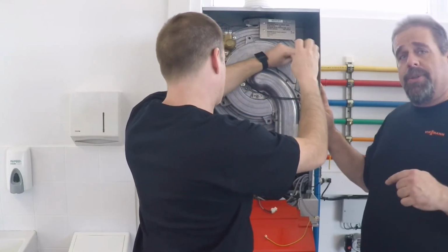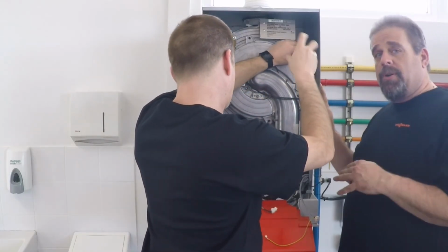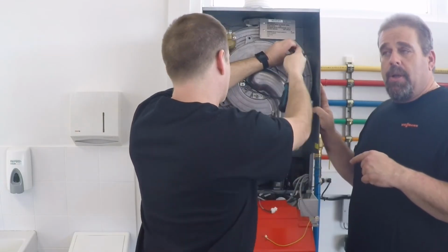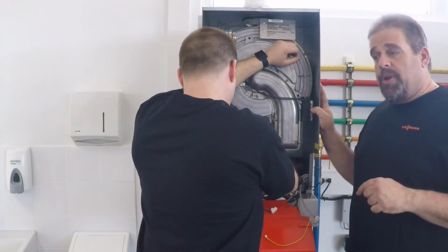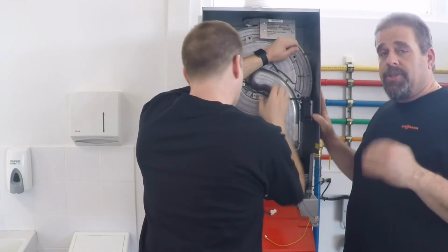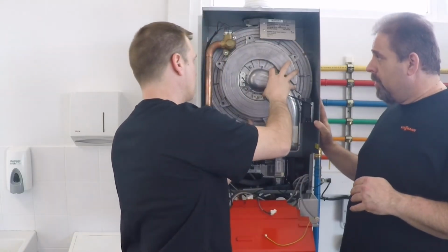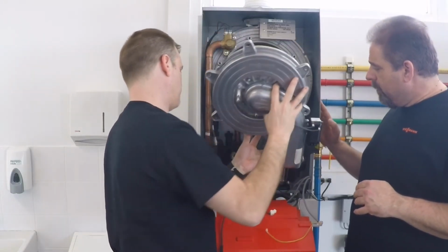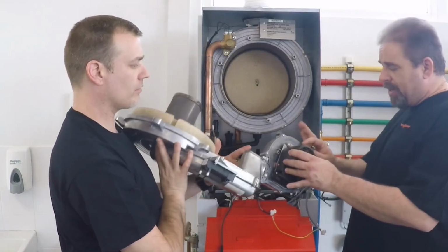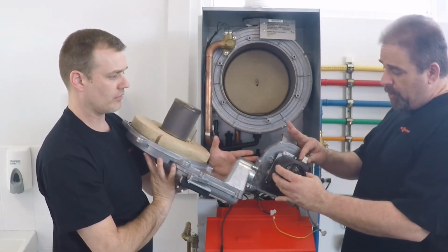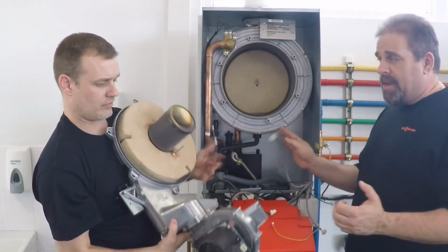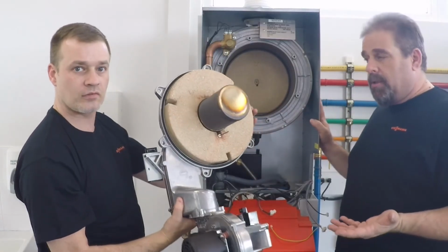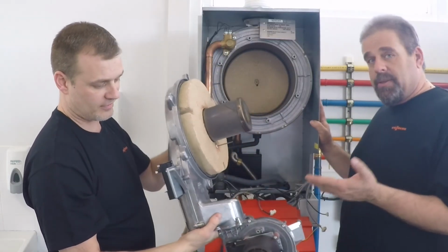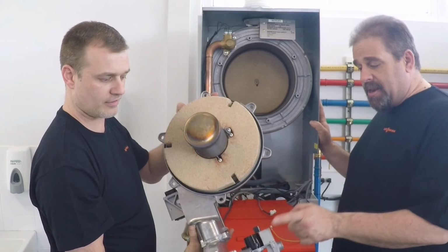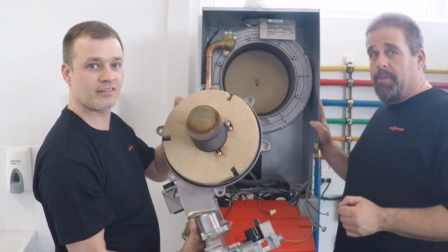So this video is going to be just removal of this burner to access the heat exchanger. Subsequent videos will show you how to clean the heat exchanger and service the burner for maintenance. So now Jay removes that burner assembly. There's also 1 Molex plug on the back side of that fan. We want to make sure we remove that. And now we can access fully our premix variable speed fan, negative pressure gas valve burner assembly.